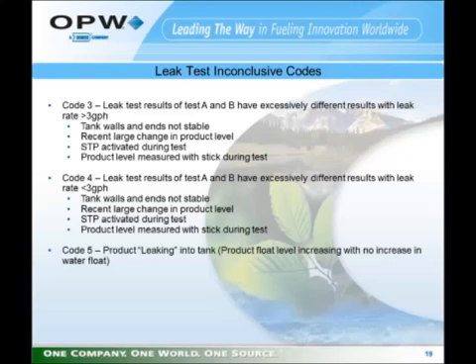An inconclusive code 5 is an indication that product is leaking back into the fuel storage tank. The product level is increasing with no corresponding increase in water level. This can be caused by a leaking check valve in a submersible pump. It can be caused by a leaking check valve for a suction pump, or it can be caused by product leaking back into the line from a vapor line or an improperly installed vent line. As mentioned earlier, an inconclusive code 5 will cause the segmented leak detection database to be stopped, emptied, and the SLD test started all over again.